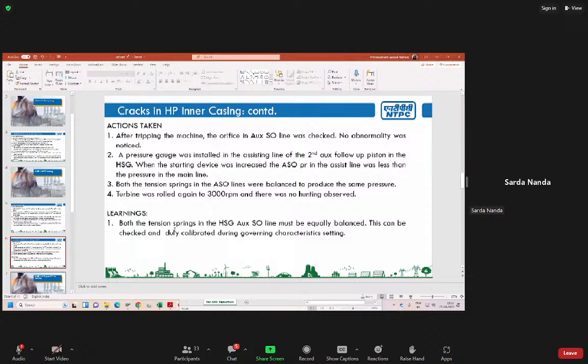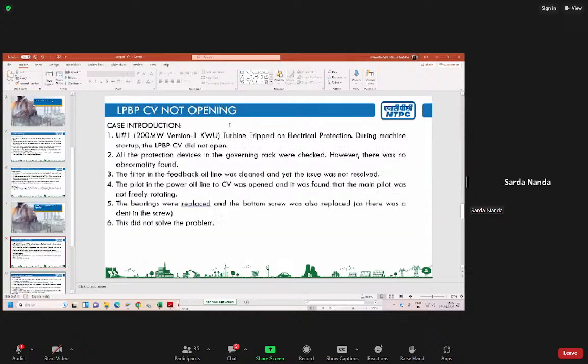But in future, whenever we are going for governing characteristics, we should make sure that there are two pressure gauges installed in both the auxiliary follow piston lines, and both the pressure gauges show the same pressure. If that is maintained, then our auxiliary secondary oil will not have any bearing on the AHC mode. Otherwise, if there is variation in the auxiliary secondary oil, then there will be a lot of problems which we will face. The third case study is again 200 megawatt, but this is version 1. It was in Korba itself.